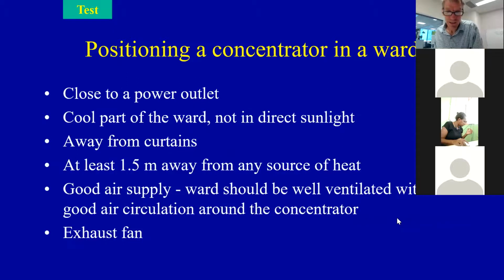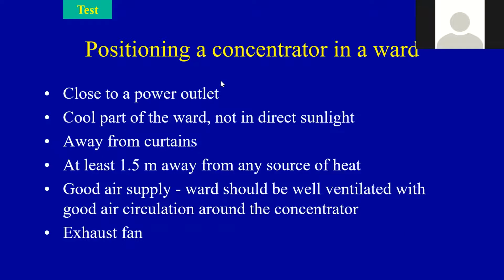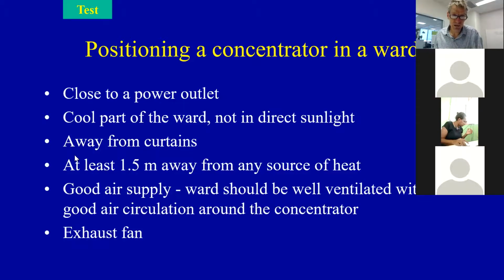Okay, a bit more about concentrators and how you set them up in the ward. Where you put a concentrator in the ward is very important. You need to have it close to a power outlet, of course. It should be in the cool part of the ward, not in direct sunlight or in a warm area close to a heater or a heat source of any sort. Keep it away from curtains. A concentrator needs to breathe. It's bringing in air from the outside. So it should be at least 1.5 meters away from any source of heat and 30 centimeters, so 1 foot, away from any wall. You need to give it space to breathe.